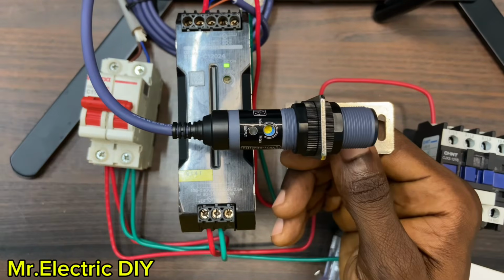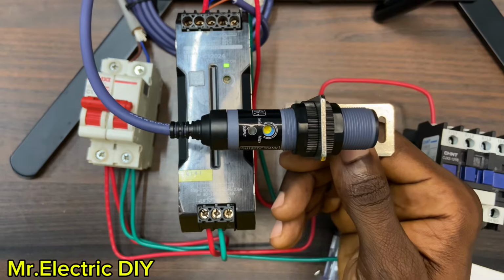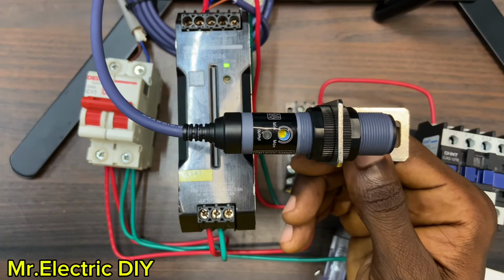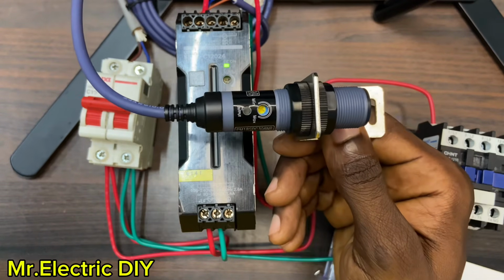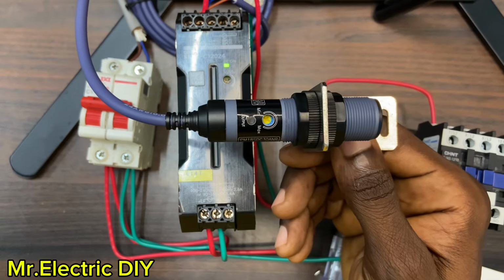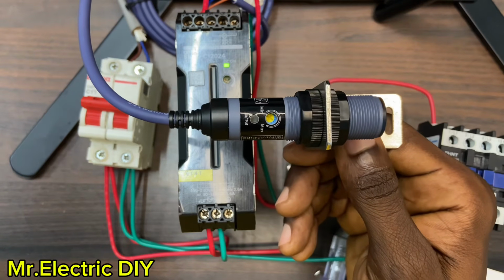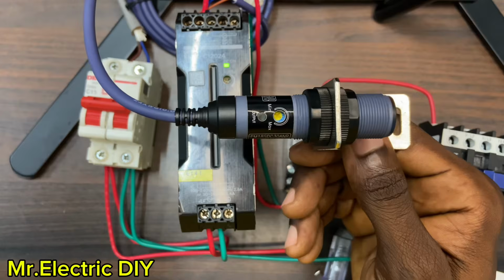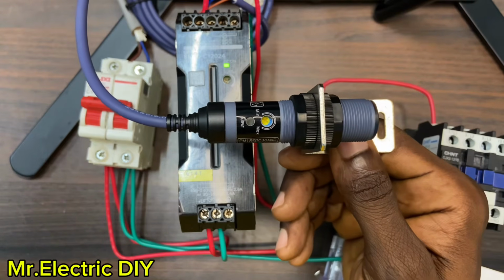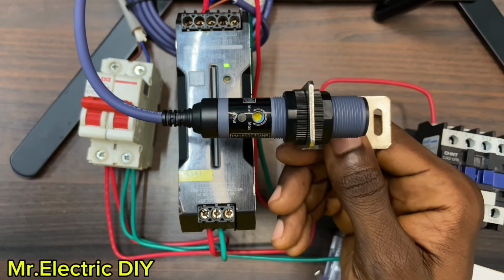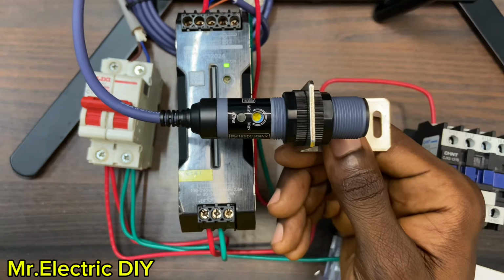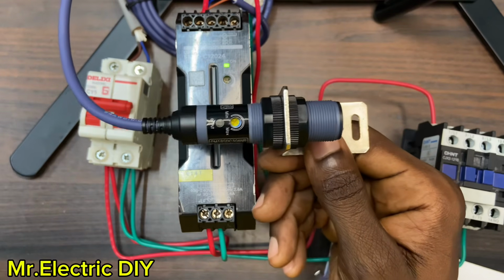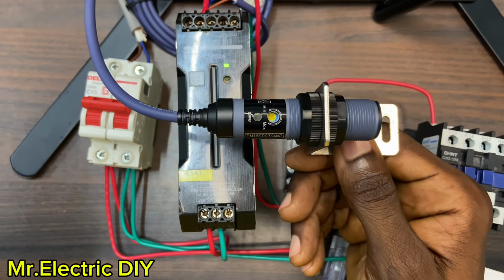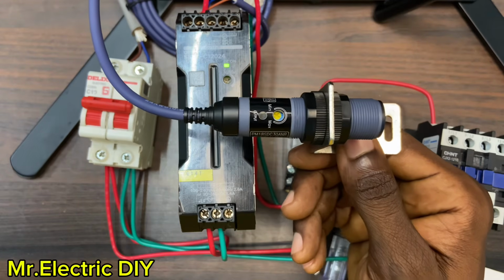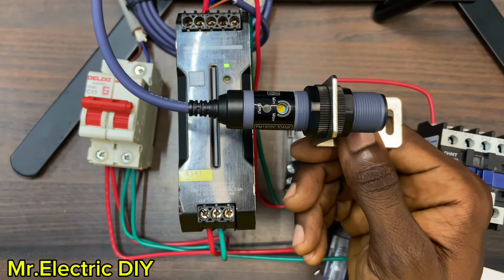With these three types — the through-beam, the retroreflective, and the diffused or reflective type — what I'm holding right now is the diffused or reflective type. The one that offers the longest sensing range is the through-beam photoelectric proximity sensor, while this type offers a shorter sensing range. So if you want the sensor with the longest sensing range, go for the through-beam. So guys, that is that.